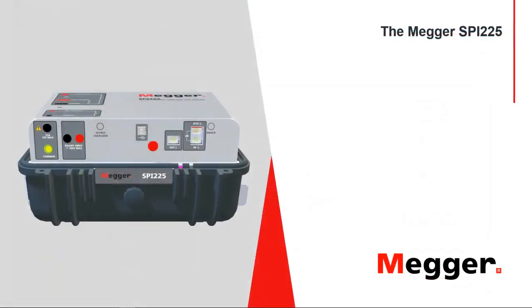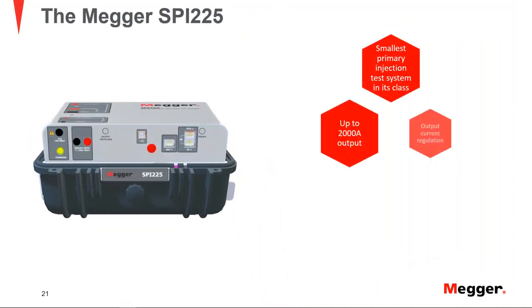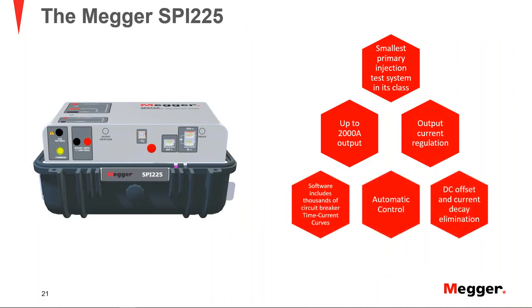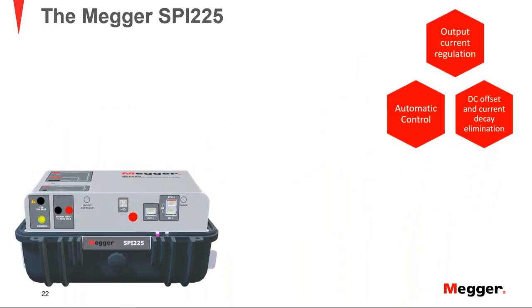Now let's look at the Megger SPI 225, right? What are the main features of the unit that will help me with these challenges that we just discussed? I will start by saying the unit is the smallest primary injection unit in its class, judging by the output capability in terms of the current that it can deliver. It is a small and light unit. Once again, the unit can deliver up to 2000 amps of short circuit current.